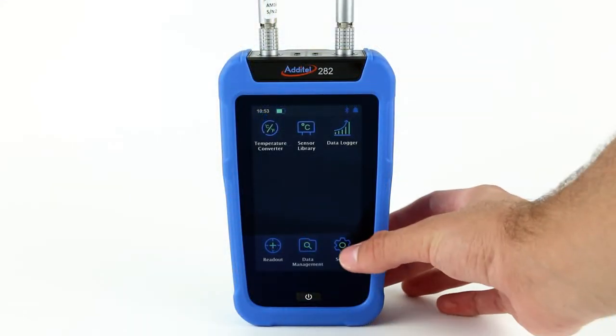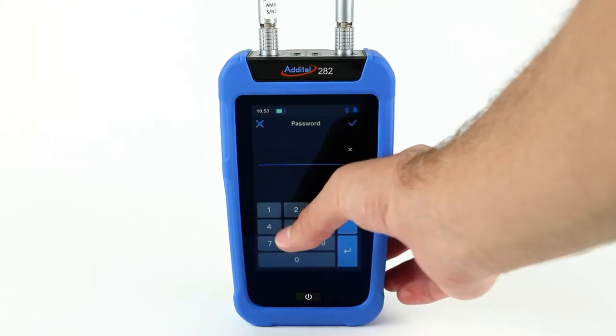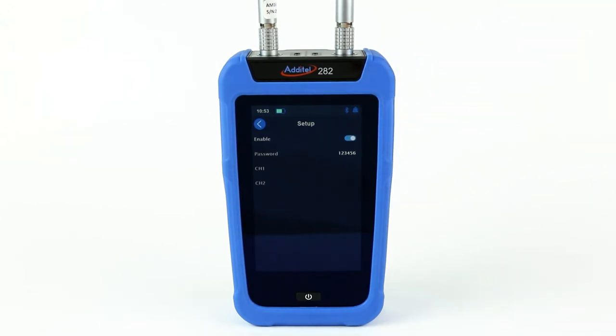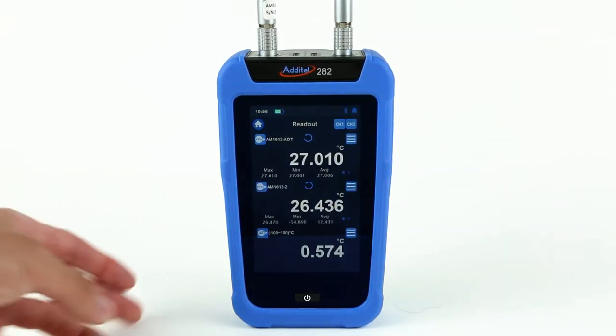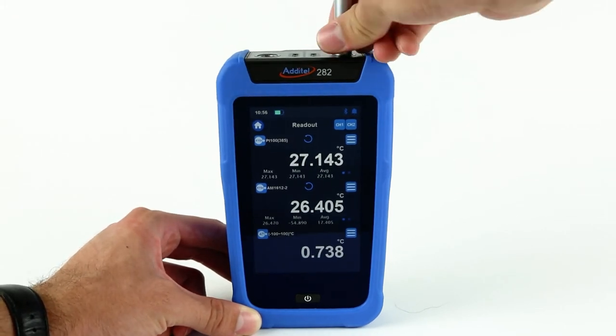The use of Additel Smart Connectors for PRTs allows for a unique probe lock feature. This feature locks a specific PRT to a specified channel where that channel can only read that PRT. This is useful for when a system calibration is performed on one specific PRT and one specific channel.